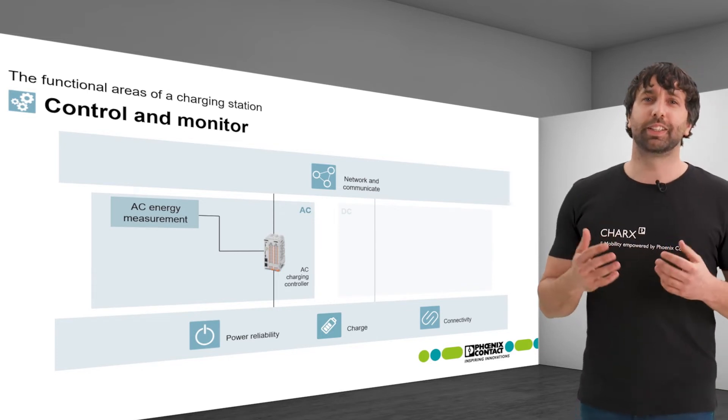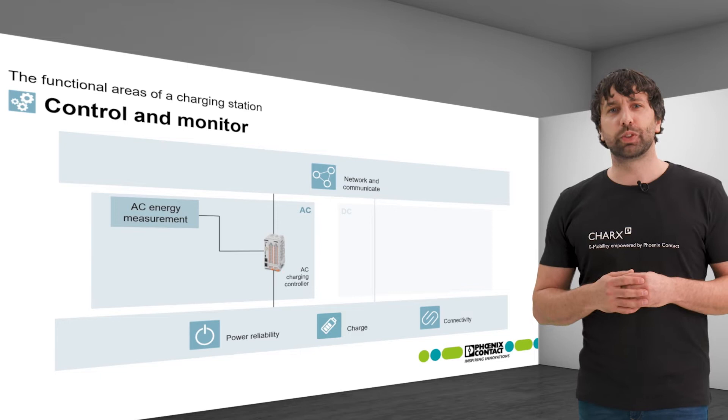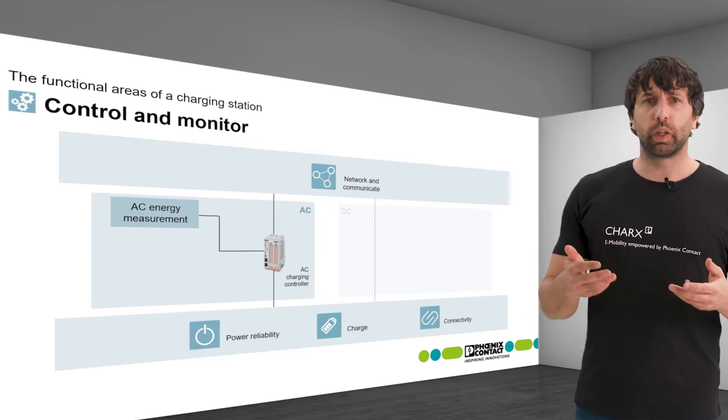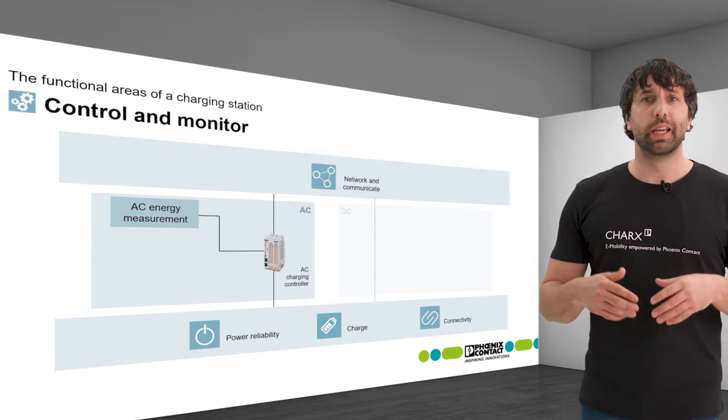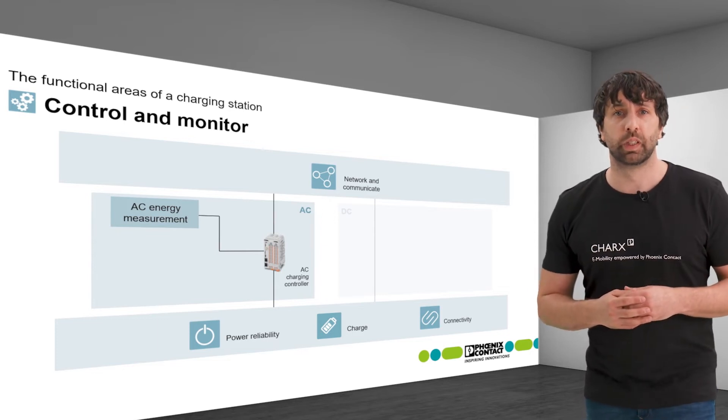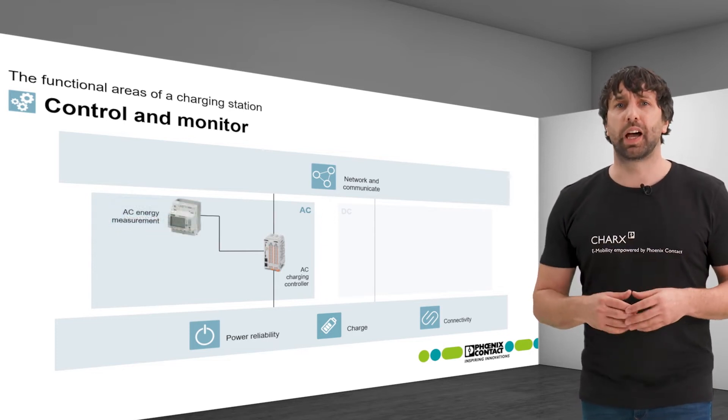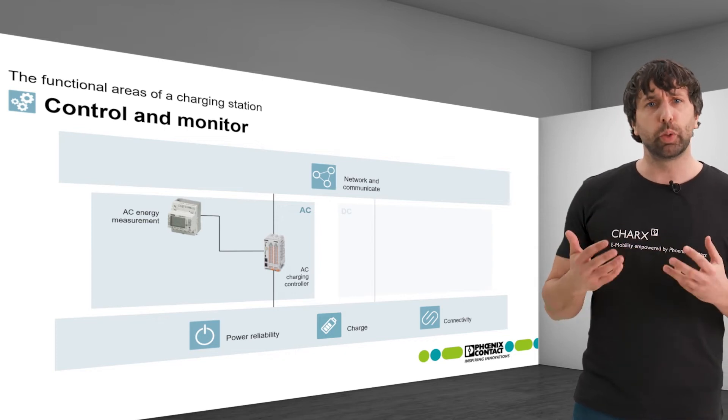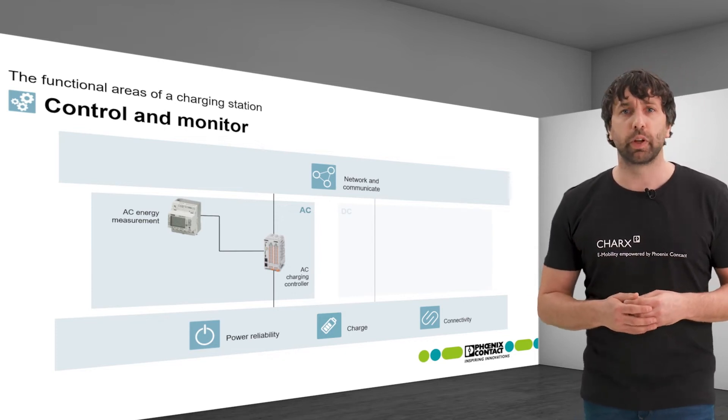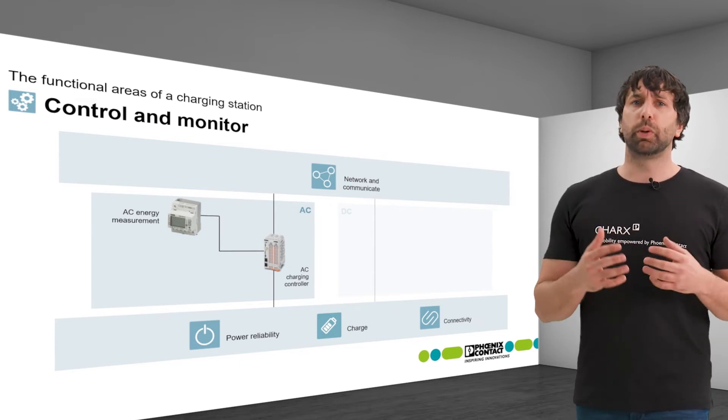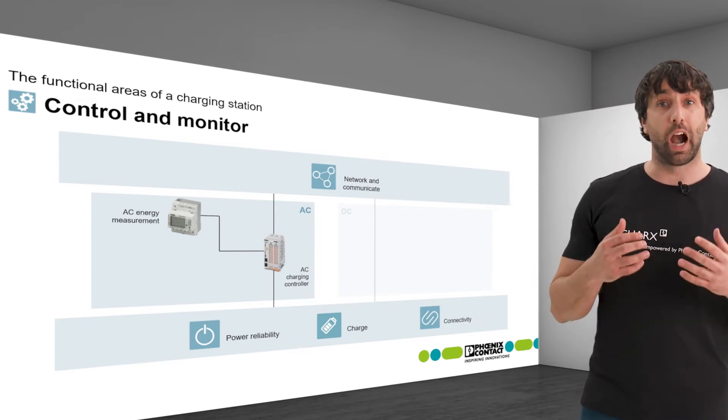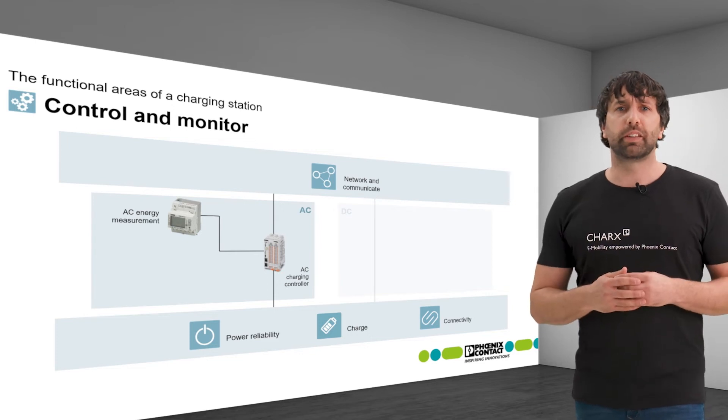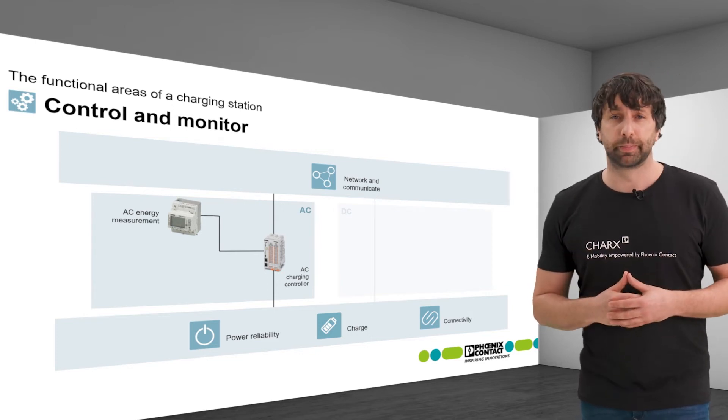In addition, the energy values can be used for safety measures. For example, the controller can shut down the charging process in case of an overcurrent. Our MPRO energy meters are MID-conforming, meaning that they fulfill the European Measuring Instruments Directive for billing processes. They are typically connected to the controller via RS485 and also offer web-based data management via Ethernet.